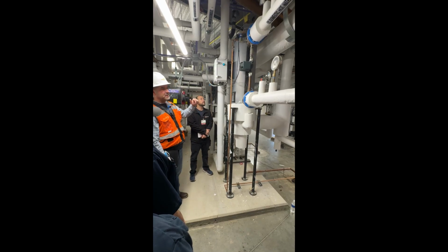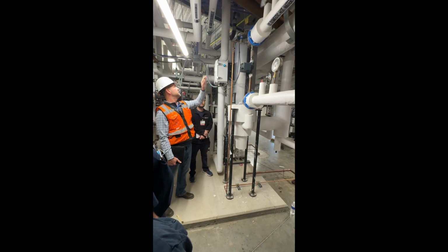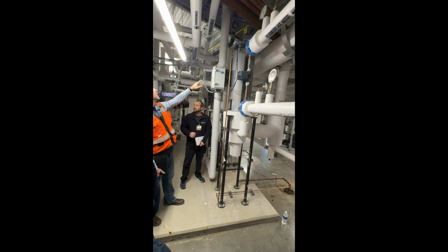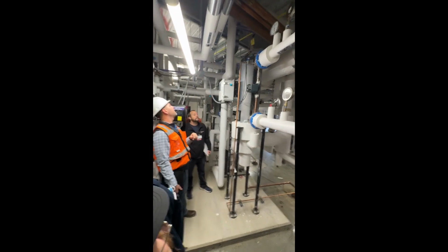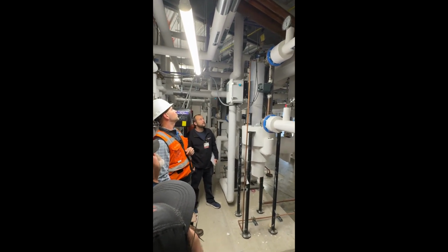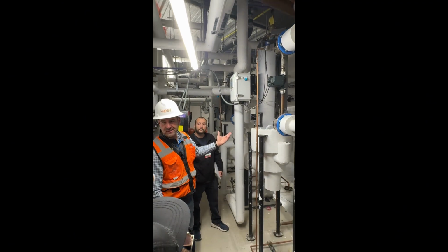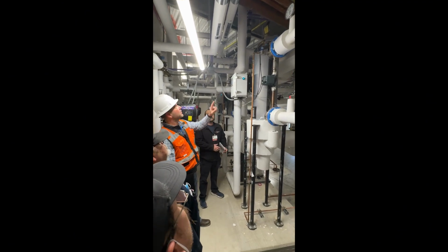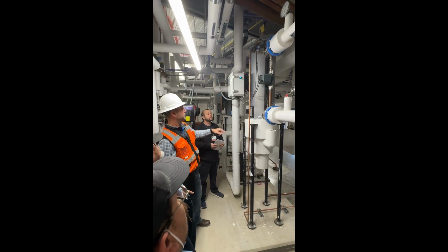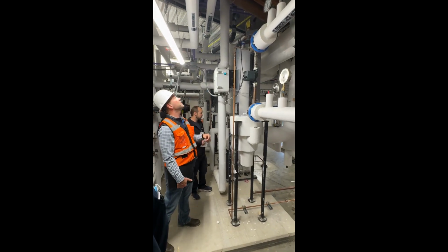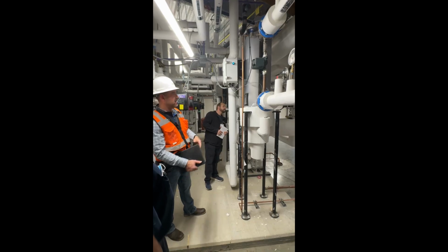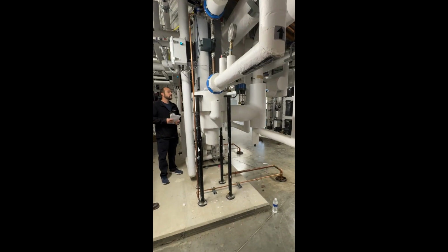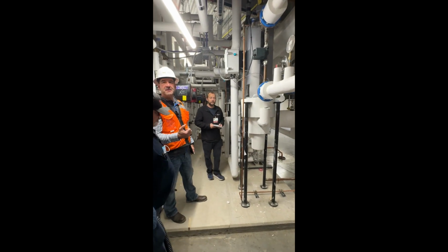As far as controllers, you got to be tall to see it. But on your control panel, it shows our set point of 125 and our outlet temp of 125, so it's holding right where it needs to be. Okay. We have a controller. Let's see, where is the pneumatic controller? I think it's on the other side. Yeah, on the back side. That's just modulating that steam controller up and down to maintain set point.